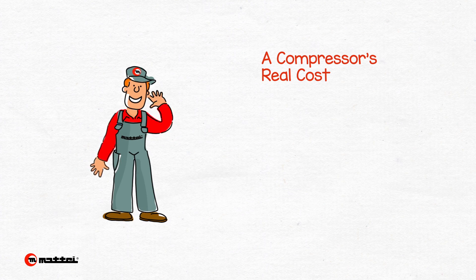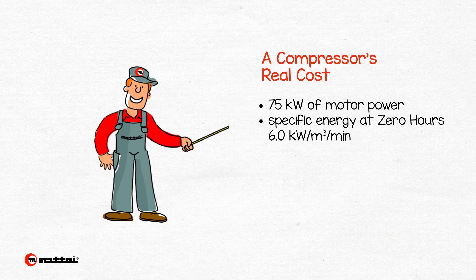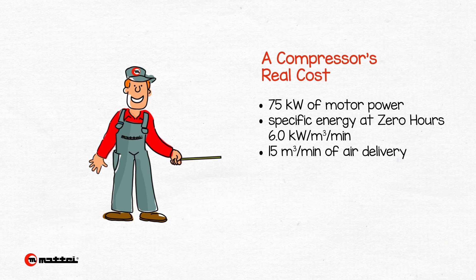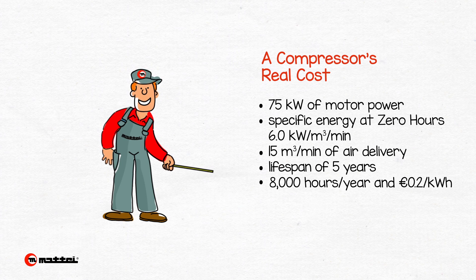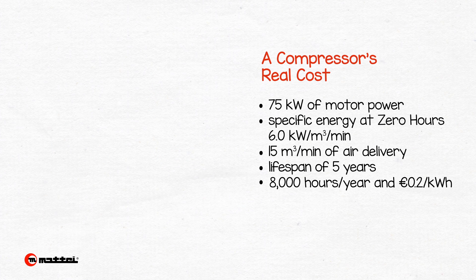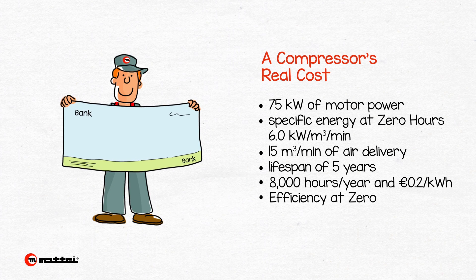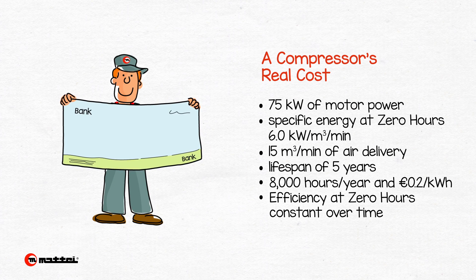Let's look at an example to clarify the difference in terms of costs and gains. Considering a 75-kilowatt compressor with a specific energy at zero hours of 6 kilowatts per cubic meter per minute and an air delivery of 15 cubic meters per minute, which will function for five years at 8,000 hours per year at €0.2 per kilowatt-hour — according to the data declared by the manufacturer's catalogues, which consider the efficiency at zero hours as constant over time, this type of compressor would cost the user €720,000.